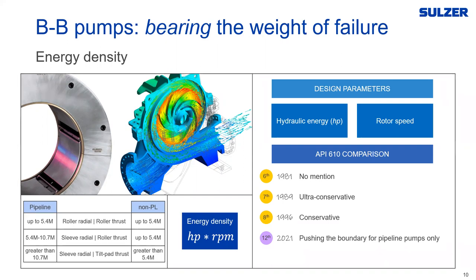Above 5.4 million in non-pipeline applications, API recommends going to a hydrodynamic bearing for the radial bearing — a sleeve radial and a roller thrust. For pipeline pumps, between 5.4 and 10.7 million you can use a sleeve radial and roller thrust arrangement, and greater than 10.7 million they recommend going to hydrodynamic for both. API's evolution toward less conservative limits reflects years of field experience and modern analytical techniques like thermal analysis and optimizing bearing housings through advanced computational methods that weren't available in the early 1980s or even the 1990s.